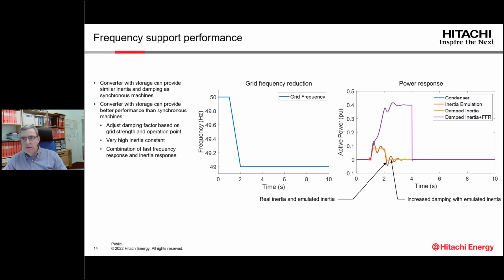But we can do even more than that. We could also increase the injected active power, and by that emulate a higher inertia, and this we cannot do at all with the synchronous condenser. And then we follow this curve here. And at 2 seconds, when the frequency becomes constant again, we could automatically go over to a fast frequency response and keep up the injected active power to increase the frequency of the grid. And in this simulation case, we continue with this until the energy storage is empty, and then the injected active power goes down to 0 again.